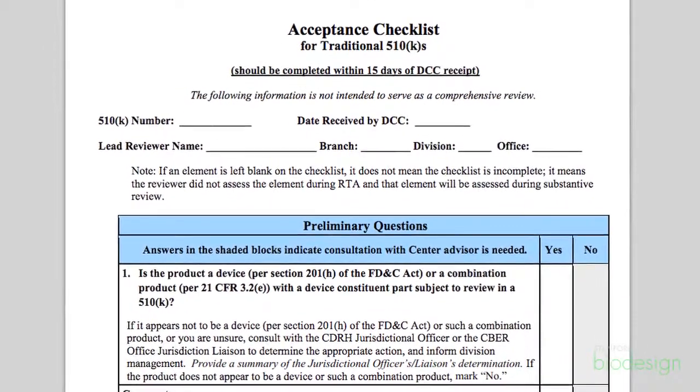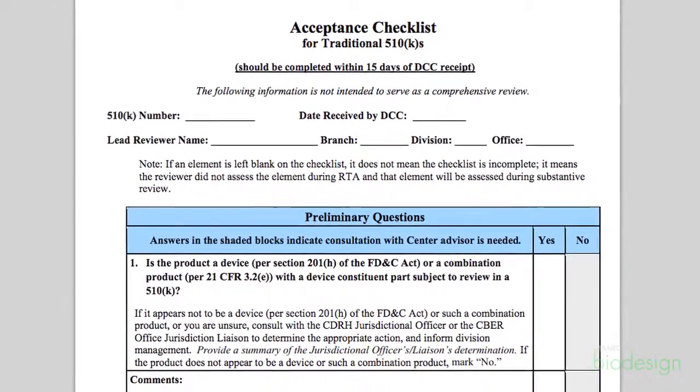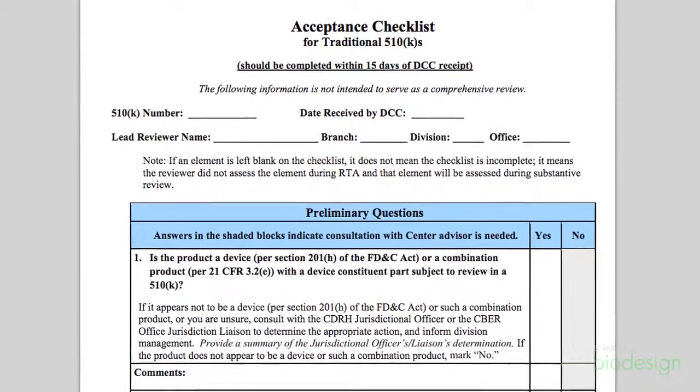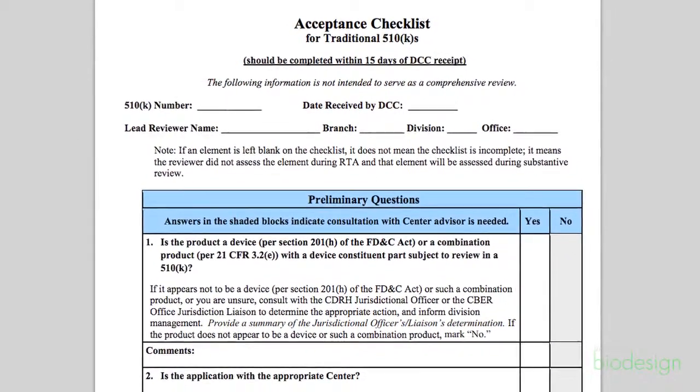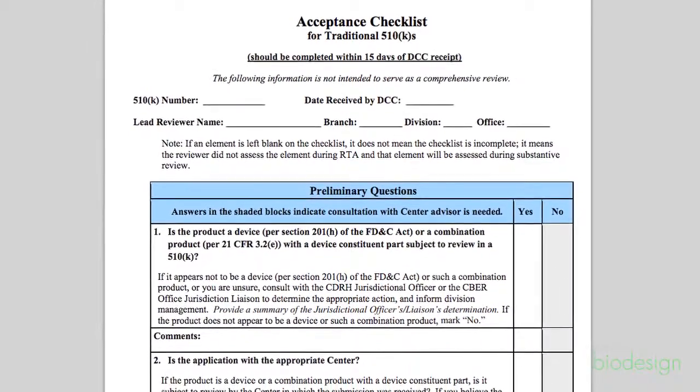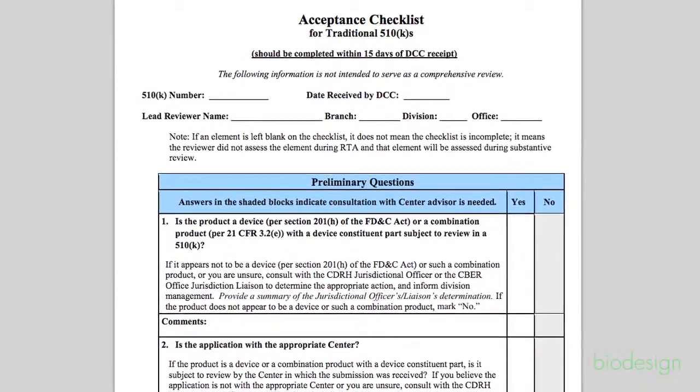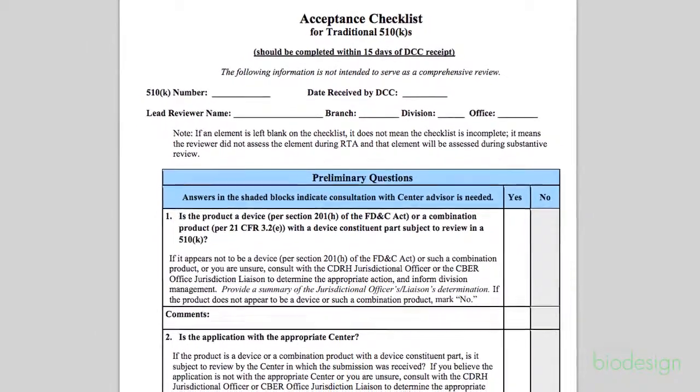There's a refuse to accept checklist for different submissions, and you can go through this checklist and literally make your narrative with the headings of everything that's on that checklist. It makes it that much easier for the lead reviewer to confirm everything has been covered. When that's not there, it's just a lot harder to get things done. I think it's mutually beneficial because a reviewer can do things very quickly and you're going to get a response a lot quicker that way.